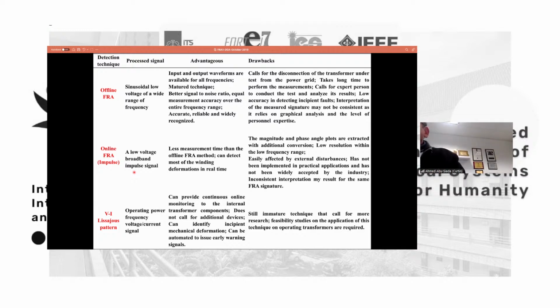And if you are using an external impulse generator, people in utilities like PLN may not allow you to do that on their operating transformer. The technique we worked on is called VI Lissajous, and the difference here is we are not conducting it at very high frequency, only at the power frequency, which is 50 Hertz, and this technique can be conducted in real time. However, it is still in the research stage.